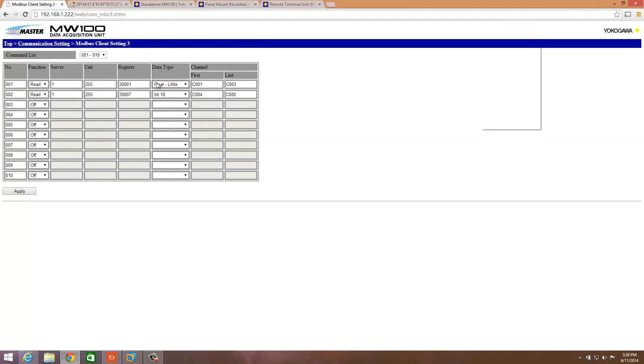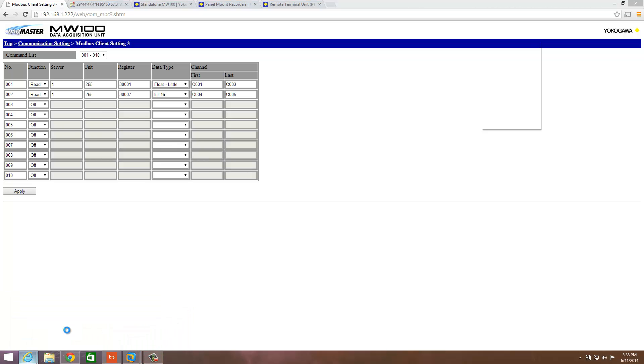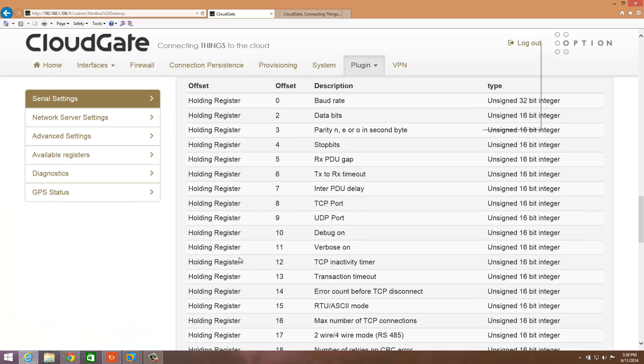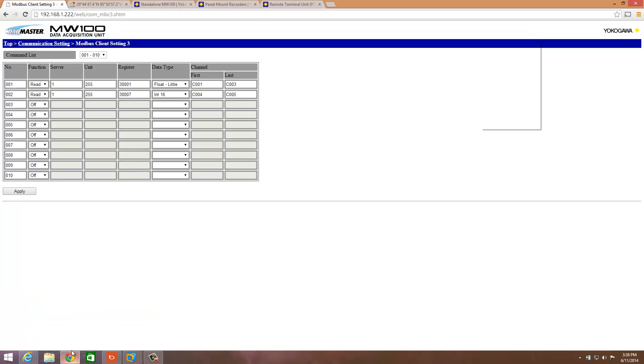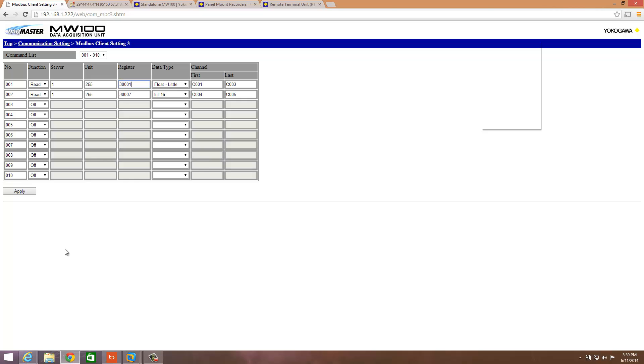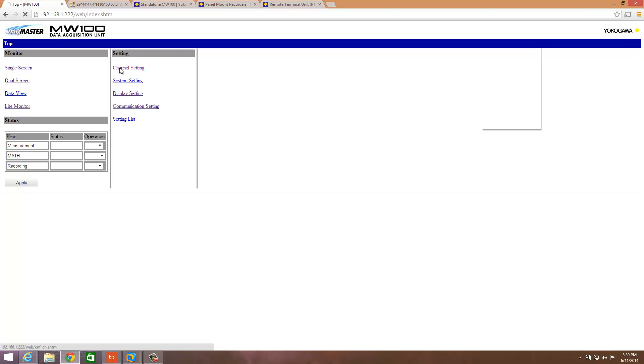What's been nice here about the CloudGate, if we go back to it quickly, is that the addresses for latitude and longitude, they're floating points and they've been blocked together, and then the integer ones have also been blocked together. So we can take advantage of that in the MW100. I'm going to do two reads here. The first server is the one we set up on the prior page. The default unit number is 255 for the CloudGate, and the register that we're going to start at is 300001. We're going to pick float, little endian data type, and we're going to go communication registers 1 through 3. This is going to read in the longitude, the latitude, and the altitude. Then we're going to do another read starting at register 300007, integer type 16, and we're going to put it into the communication registers.